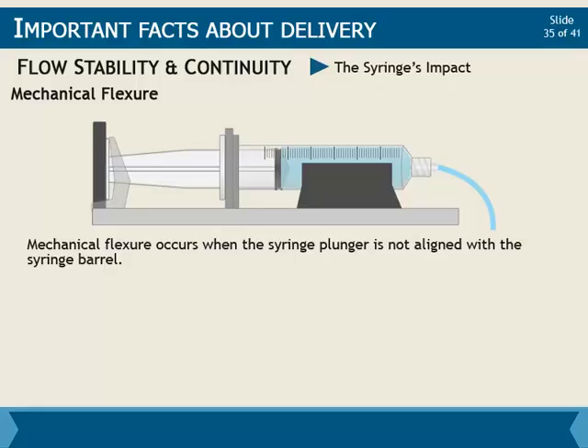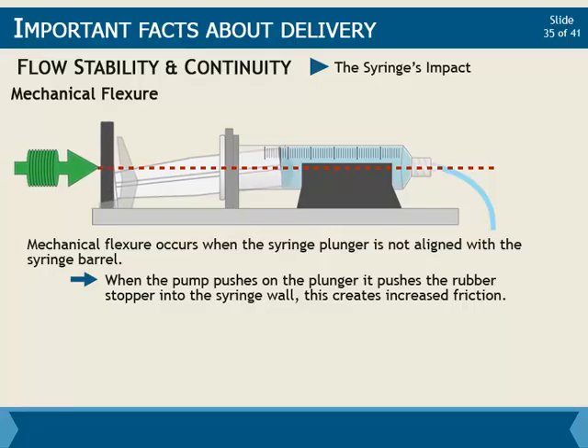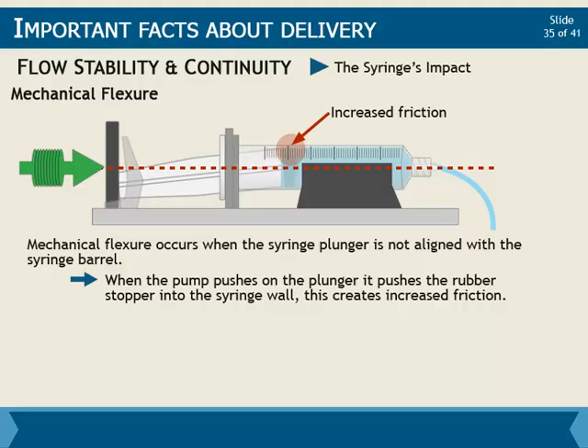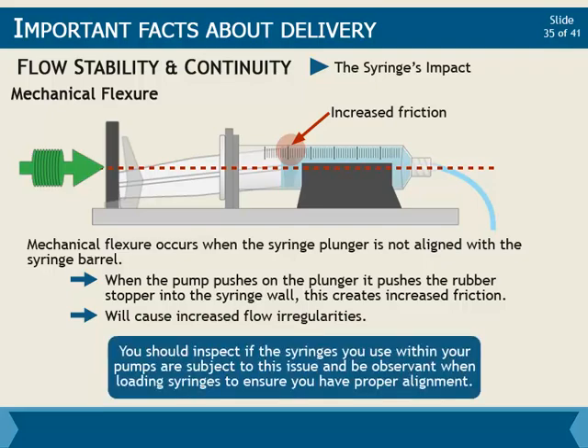Mechanical flexure occurs when the syringe plunger is not aligned with the syringe barrel. If the pump's capture arms hold the plunger at a slight angle, such that when the pump pushes on the plunger, it pushes the rubber stopper into the syringe wall, this creates increased friction. This in turn will cause increased flow irregularities. Small syringes are particularly susceptible to this problem because of the way in which they may be grasped by the syringe capture arms. You should inspect if the syringes you use within your pumps are subject to this issue, and be observant when loading syringes to ensure you have proper alignment.